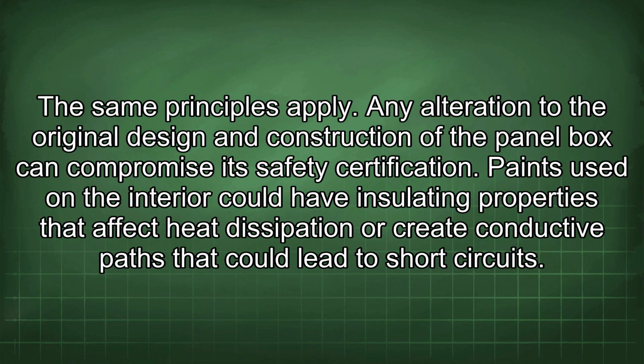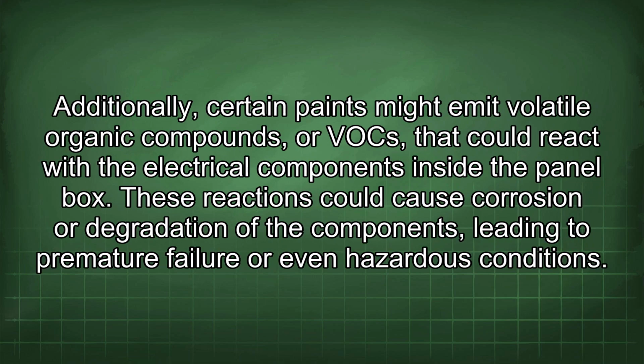The same principles apply. Any alteration to the original design and construction of the panel box can compromise its safety certification. Paints used on the interior could have insulating properties that affect heat dissipation or create conductive paths that could lead to short circuits. Additionally, certain paints might emit volatile organic compounds, or VOCs, that could react with the electrical components inside the panel box. These reactions could cause corrosion or degradation of the components, leading to premature failure or even hazardous conditions.